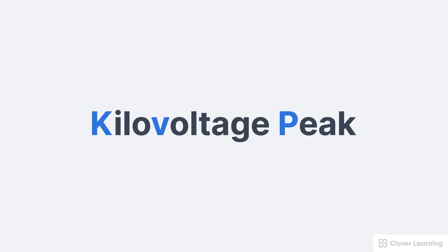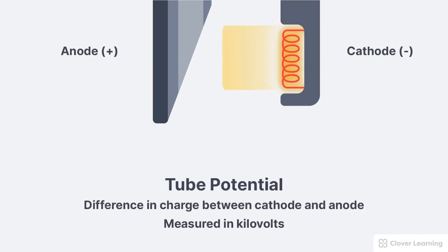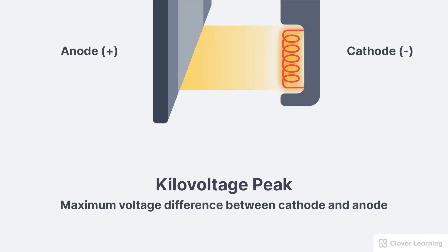The KVP is what accelerates electrons and forces them through the x-ray tube. During an x-ray exposure, the cathode is negatively charged and the anode is positively charged. This difference in charge is called the tube potential, or potential difference. We measure the tube potential in units of kilovolts, which is why this technical factor is called the kilovoltage peak.